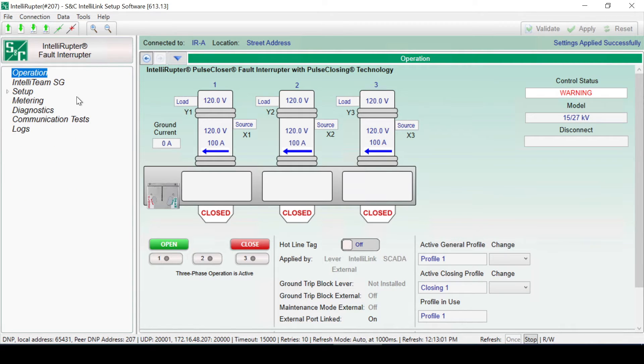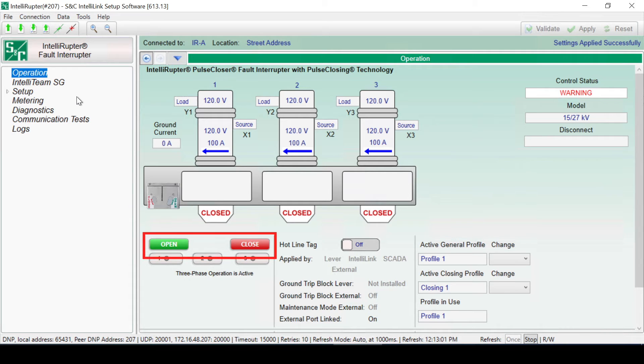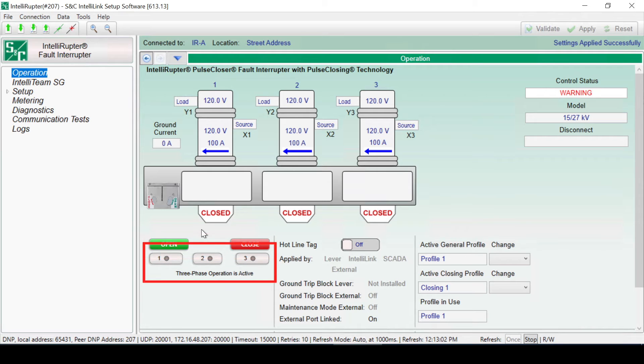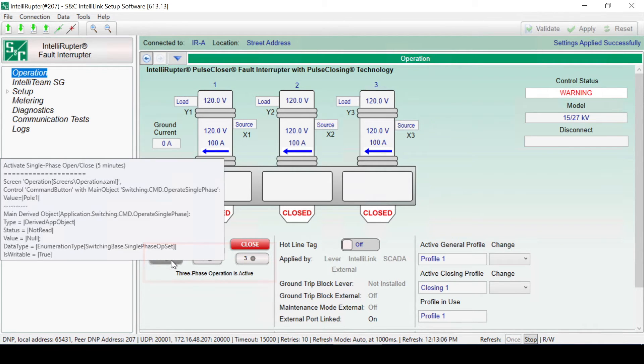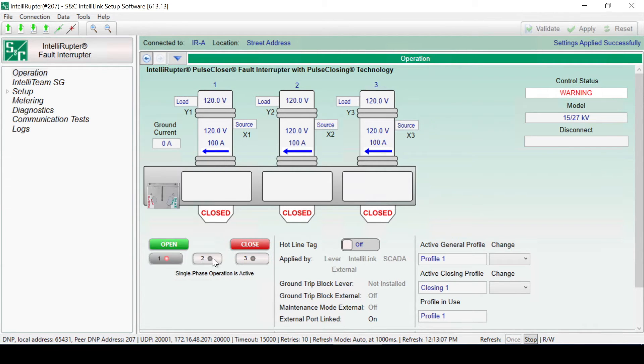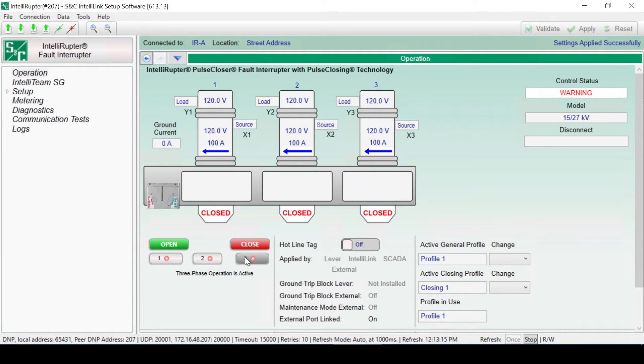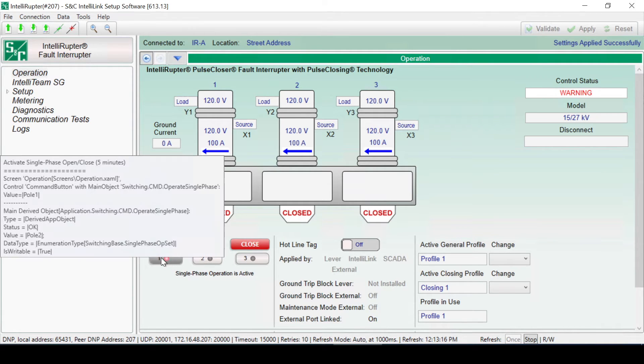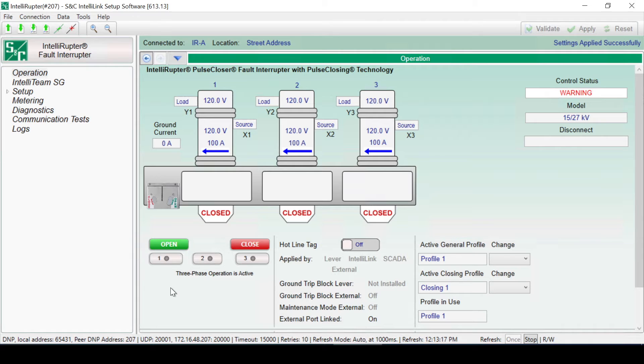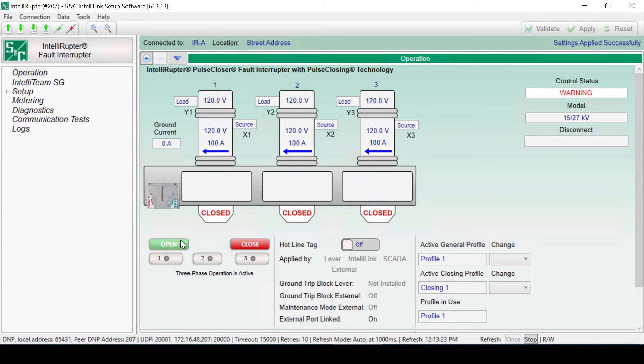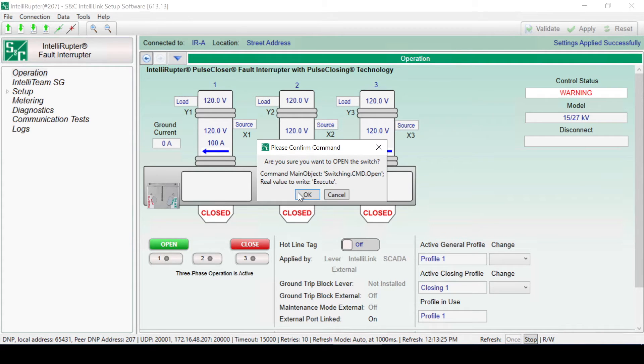The fault interrupter can be operated from the Operations screen using the Open and Close buttons. There is a button for each phase below the Open and Close buttons. These buttons will enable or disable operation for each phase. An Open or Close command will always execute three-phase operation if all three phases are either all-selected or deselected. Single-phase or two-phase operation can be selected by enabling only one or two of the phases.